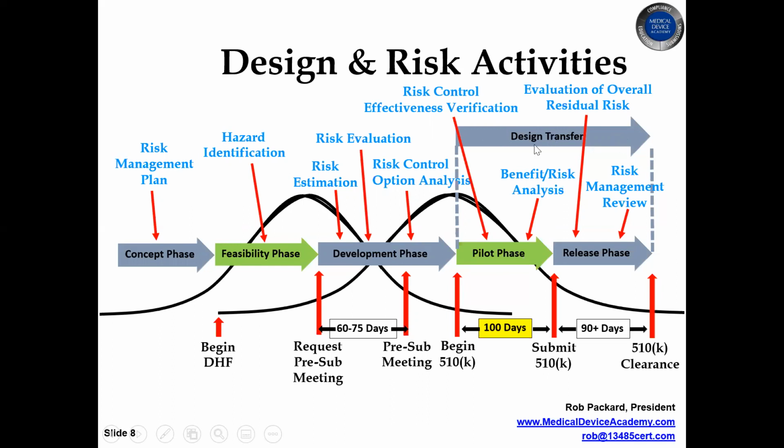If you have a very simple process, it's a 510(k) device and it's a Class 2 device in Canada and a Class 2A product in Europe, it could be very quick and you might not have to do any clinical studies, and you could potentially launch it in all three countries simultaneously. But typically this takes a while, months of time to complete design transfer.